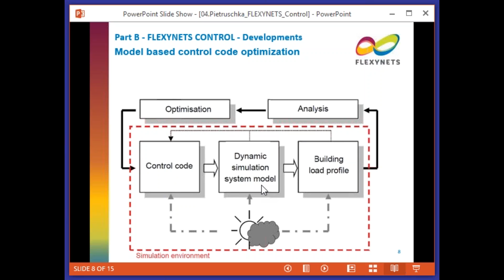So how do we arrive at this optimized control? We use simulation tools to test the control of the single substations, which are quite complex when you have prosumer stations that provide heat and take heat from the network. These are built up in simulation models. We have models of demand and a control strategy implemented in low-level controllers, which can be tested in a simulation environment and optimized before being installed on site. This is an optimization of the more or less low-level control strategy.